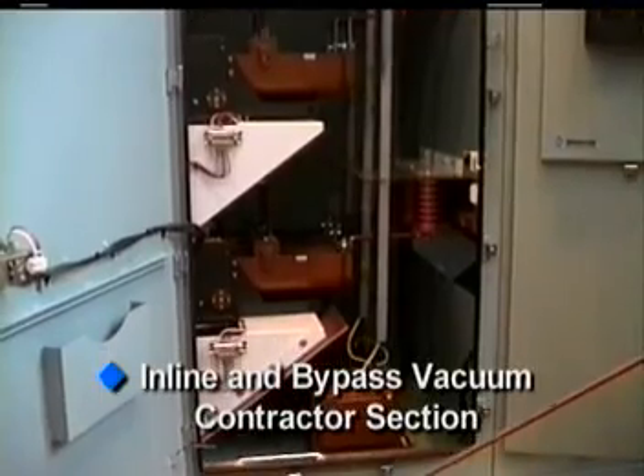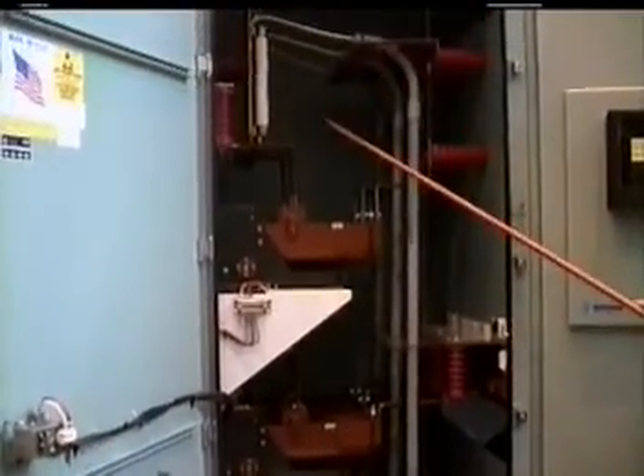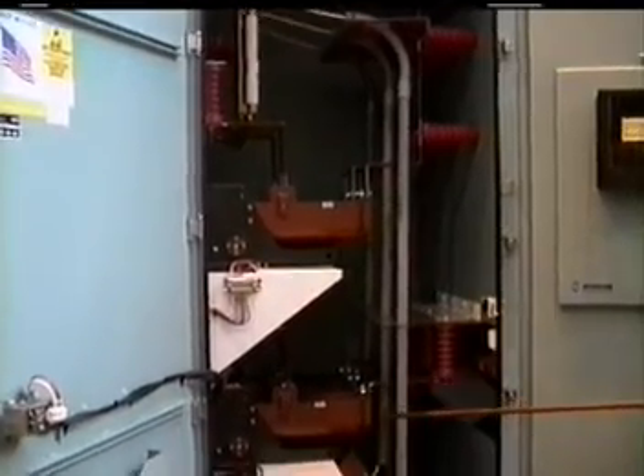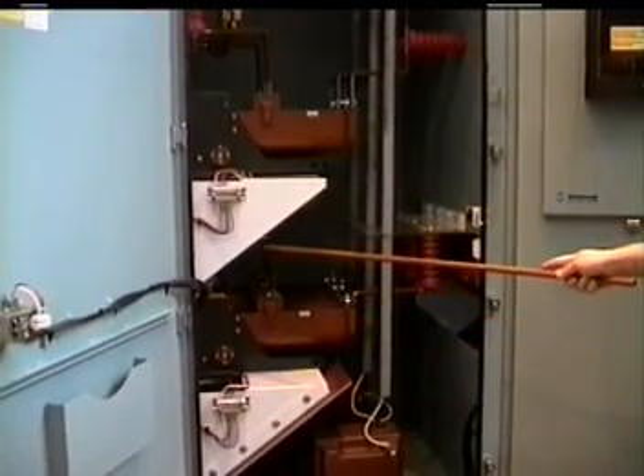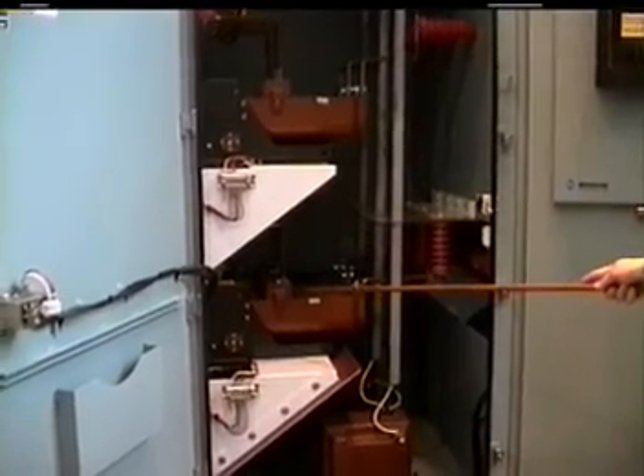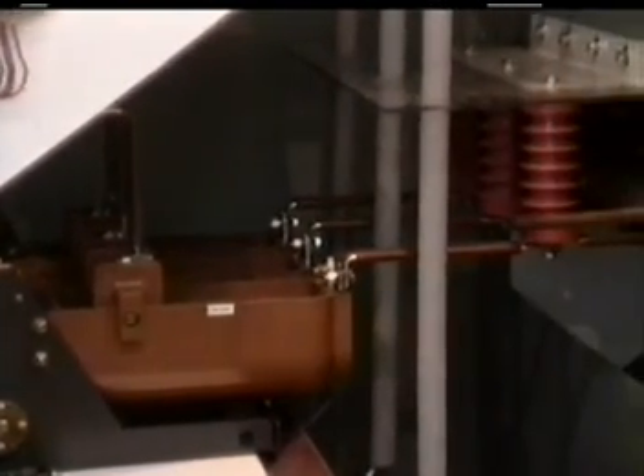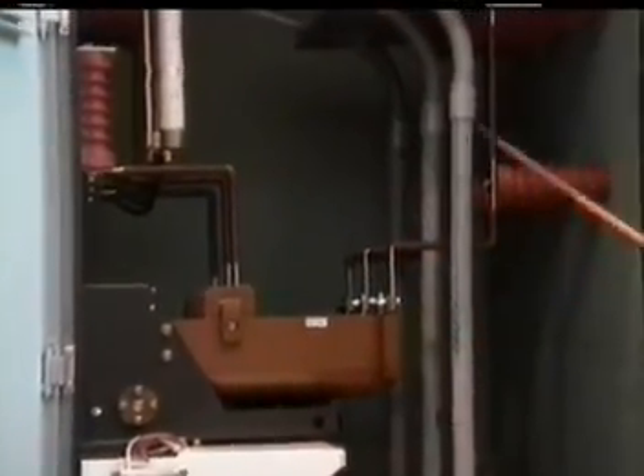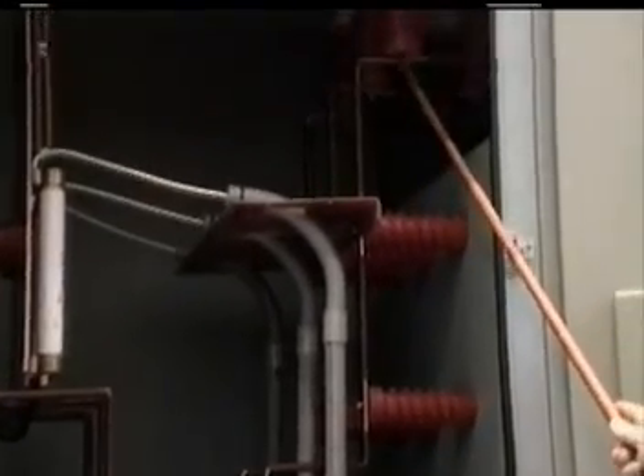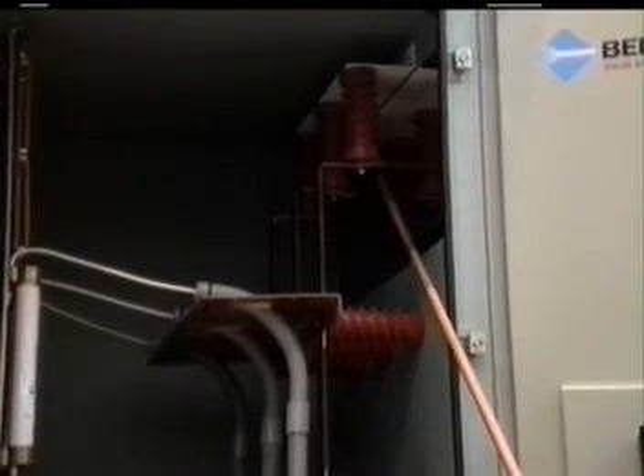Okay, from the filter section, we then pick up power for the input to the stack through the contactor section. As we said earlier, this is the input power connection along here to the inline vacuum contactor, and from the output of the vacuum contactor we go to the input section of the solid state AC switch. Up here is the bypass contactor, which basically connects the run bus into the motor T leads after we're up to full voltage. Up in this section over here we go to the output section of the solid state starter, so this becomes the motor T lead connection.